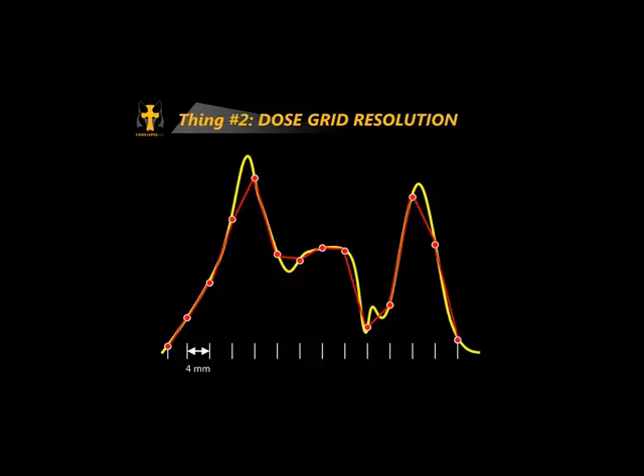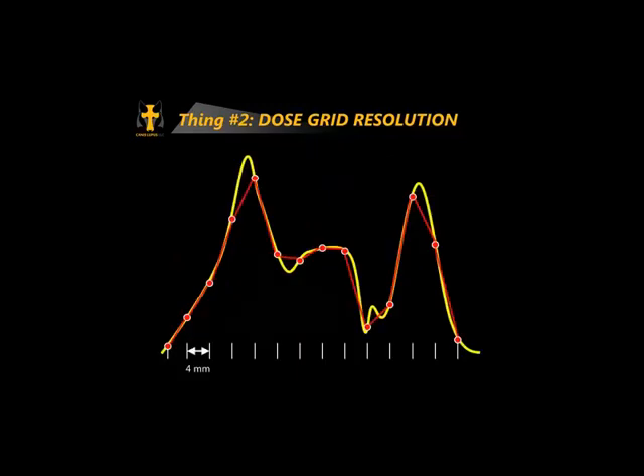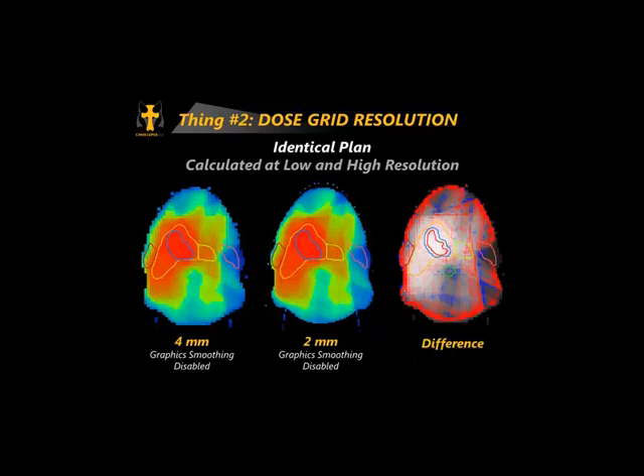Think about it: for most MLCs, leaf widths projected to isocenter are 5mm or 4mm — for some older MLCs, 10mm. For a Varian 120-leaf MLC, the center leaves are 5mm projected to central axis. If we're only sampling dose every 4mm, that's not nearly enough to capture the gradients. Here is an identical plan calculated at both 4mm and 2mm — the difference shows quite large dose variations. When you calculate at low resolution, then interpolate between dose grid points to get DVH or dose profiles, you throw away a lot of peaks and valleys.